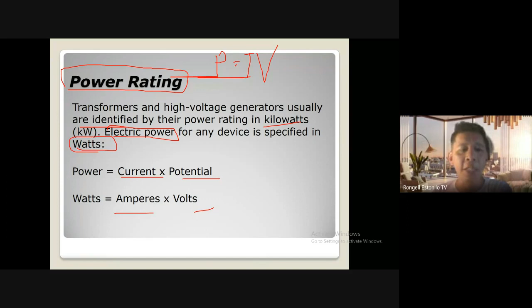Therefore, electric power for any device is specified in watts, same as discussed previously. A high voltage generator for a basic radiographic unit is rated 30 to 50 kilowatts, while generators for interventional radiology suites have higher power ratings up to 150 kilowatts. To compute the power rating, if it's already in kilovolt and milliampere, there's no need to convert one form to another - the product will automatically give you the power rating.